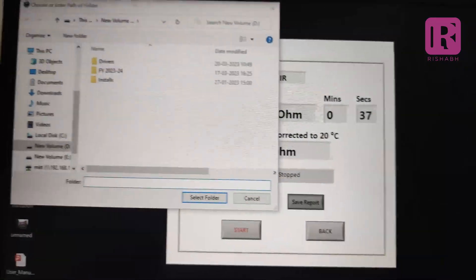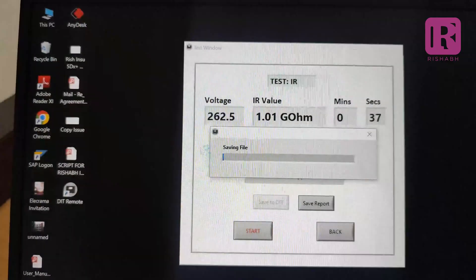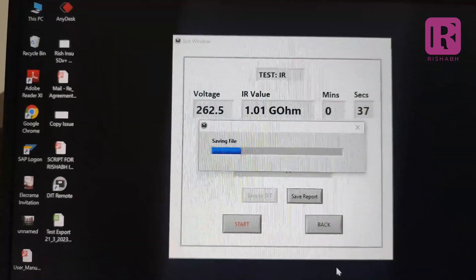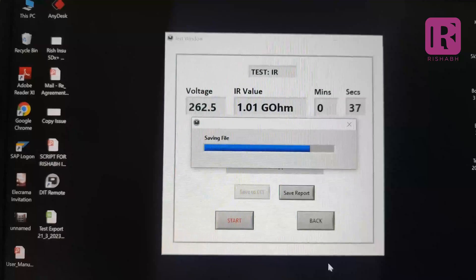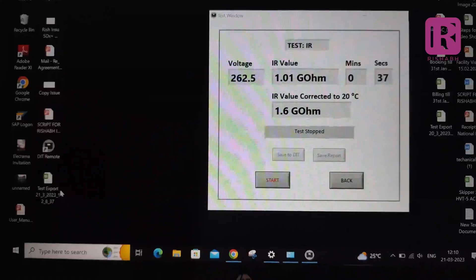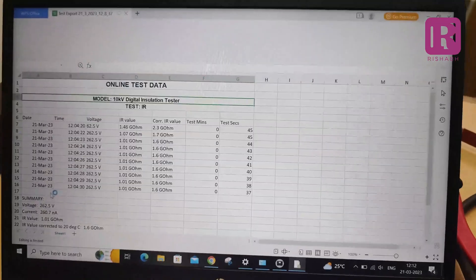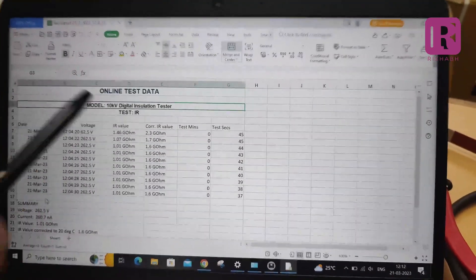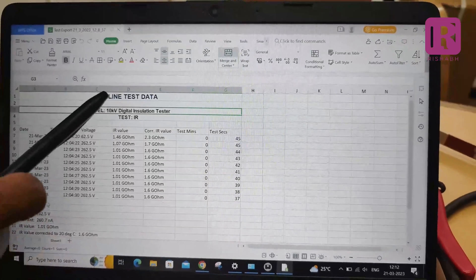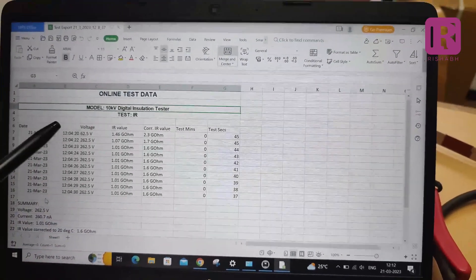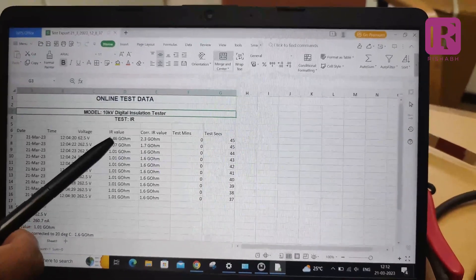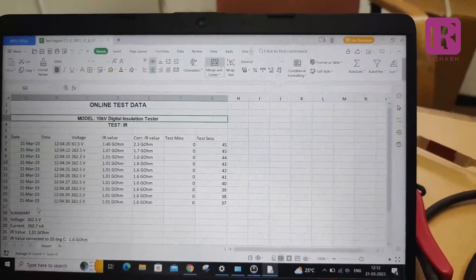After pressing the save report tab, the excel file is generated which can be saved in the laptop. In the excel file, you can see model 10KV test name i.e. insulation resistance test under online test data with date, time, voltage, IR value, corrected IR value at 20 degree Celsius.